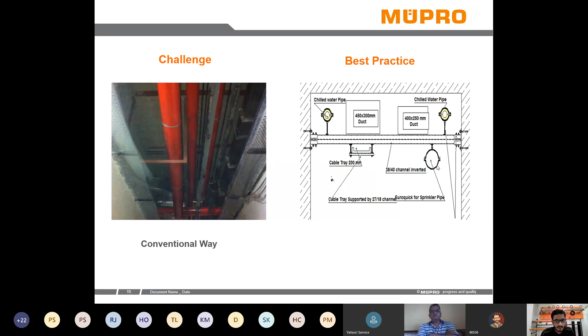But while you use a MUPRO support system, you can see a single channel installed along the length can be used for supporting chilled water, ducting, cable tray, firefighting, and water pipes. All the services can be supported from a single support channel. And while you would use n number of anchors over here, you would be using only 4 anchors for supporting all these services. This is how it gives you an advantage of supporting your multiple services in very little space.